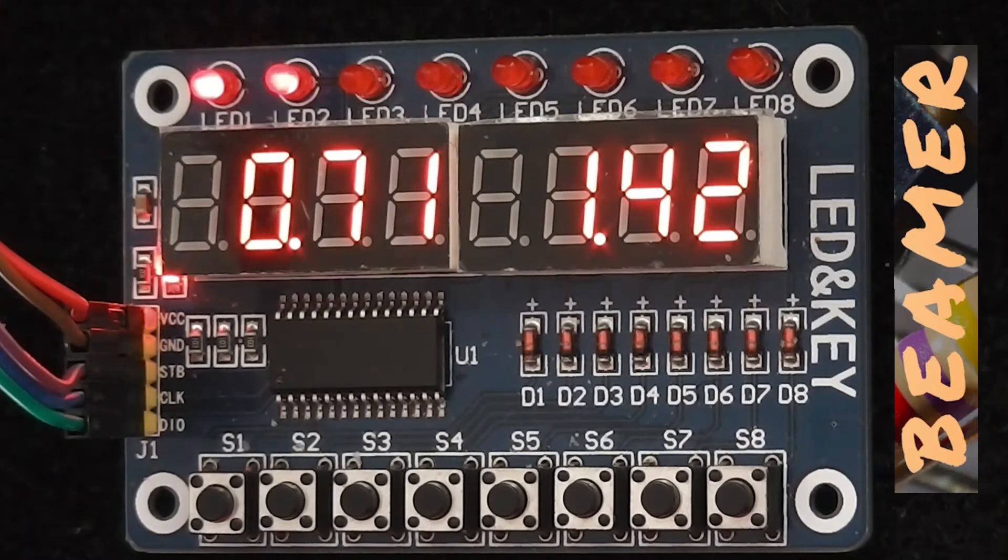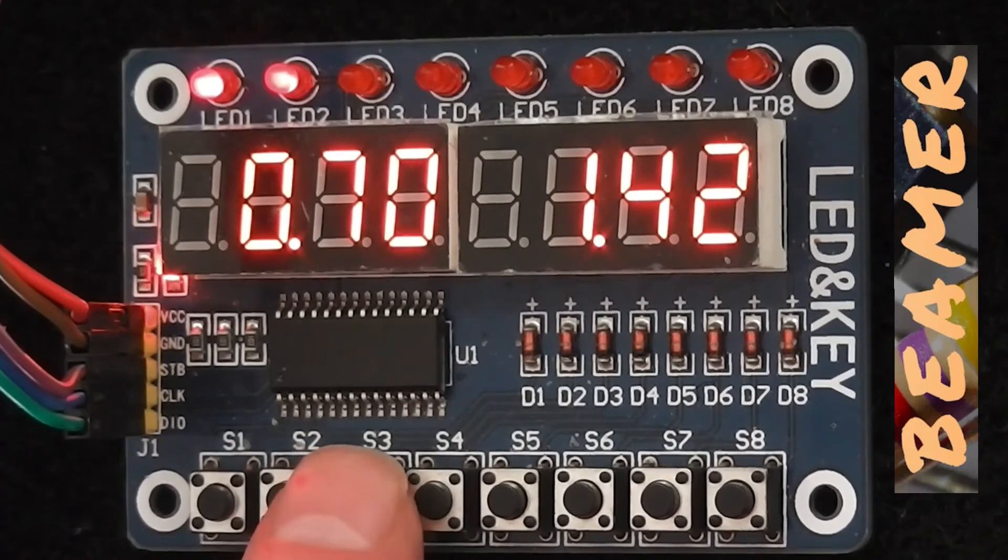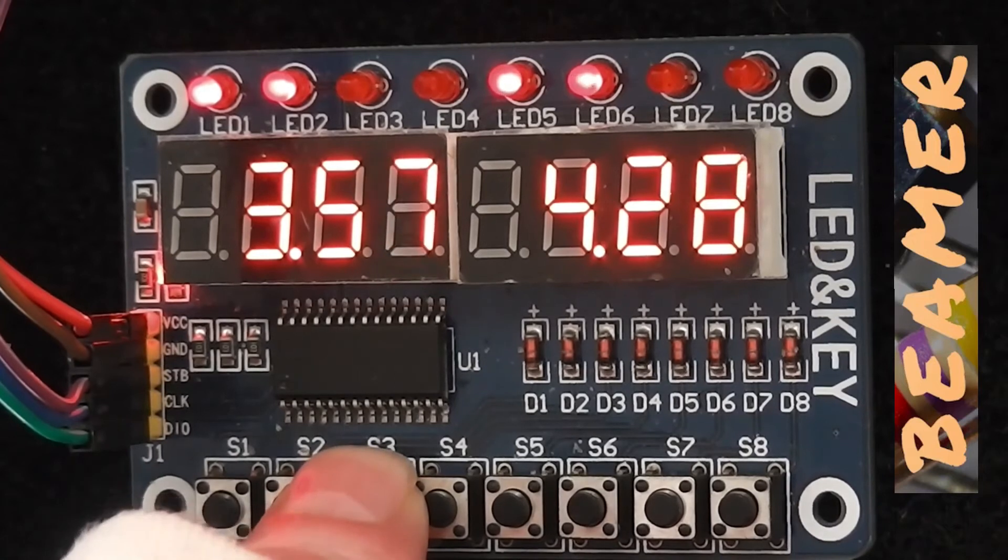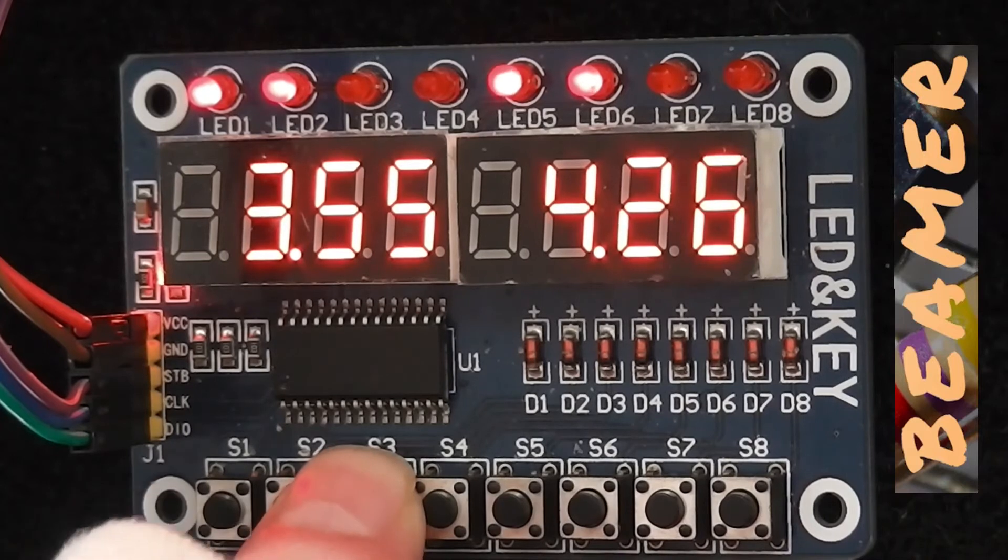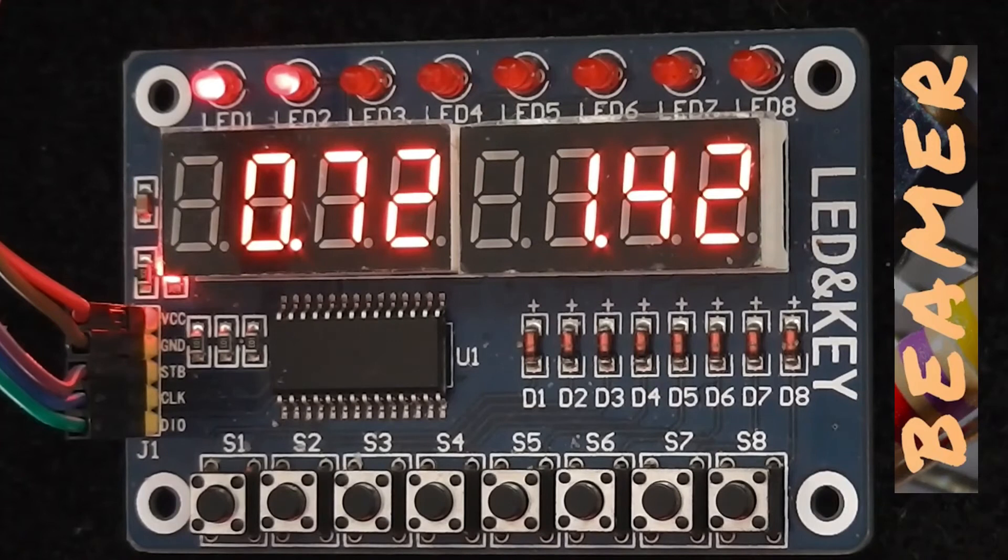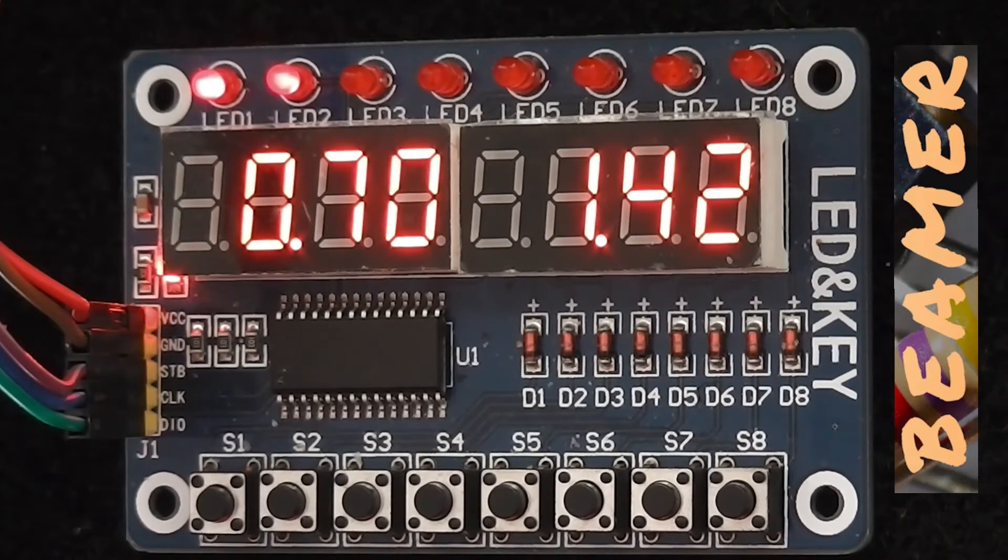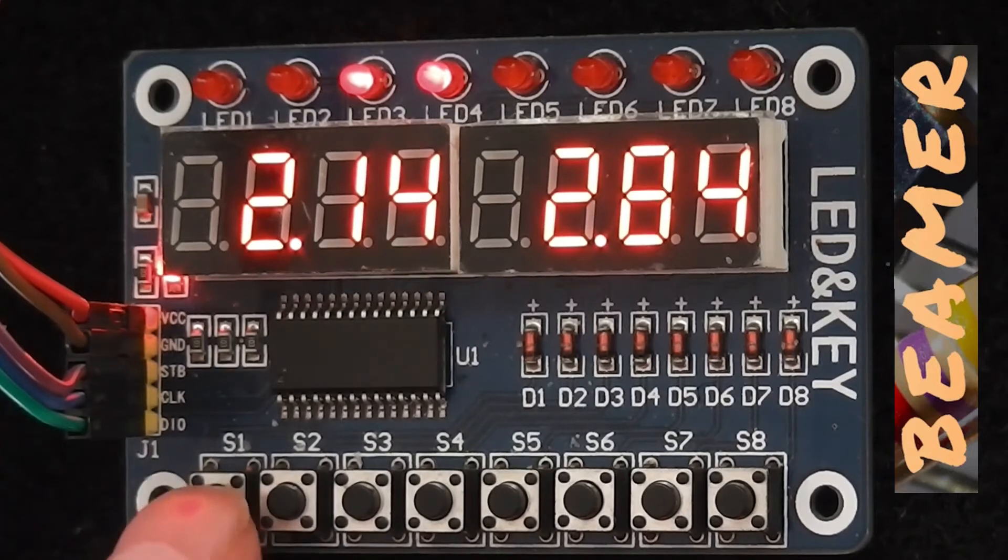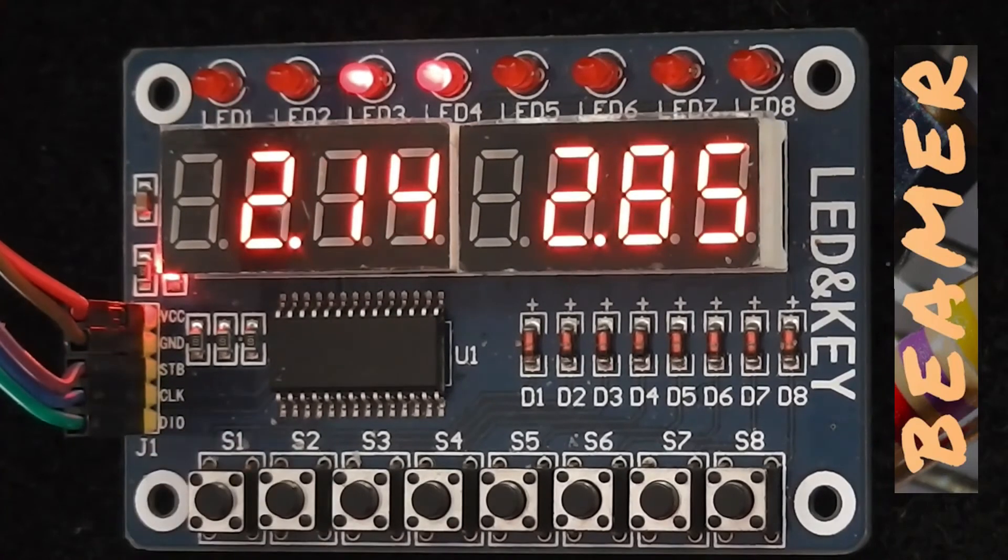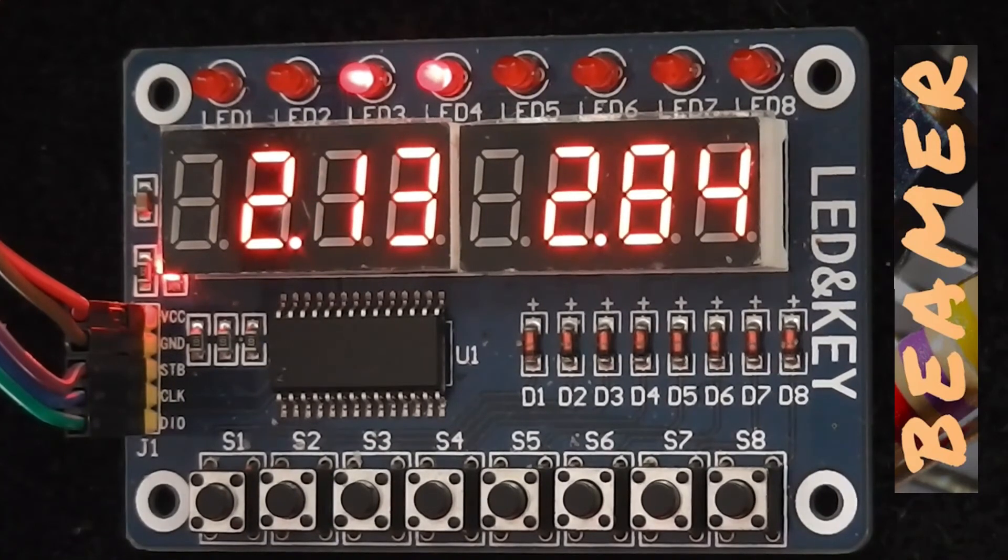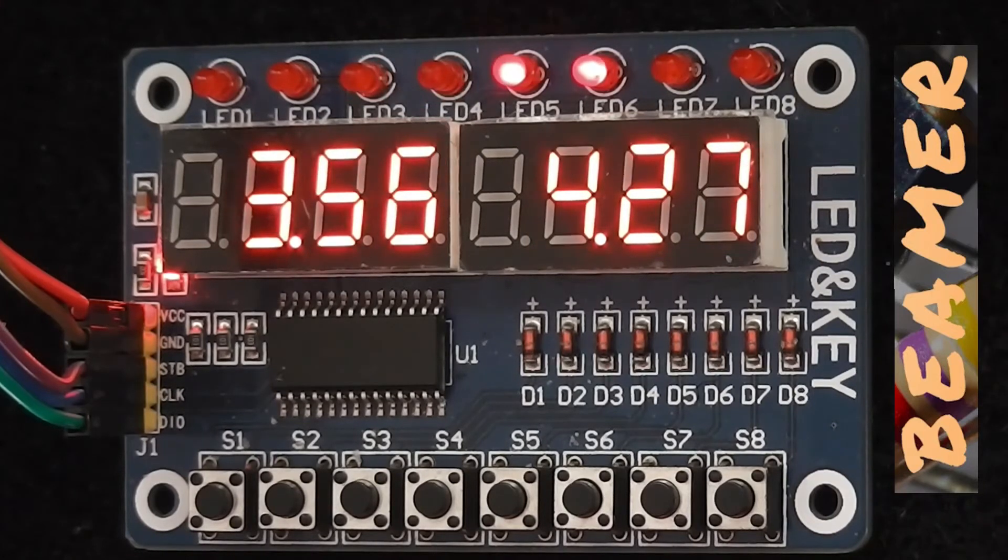If I want to look at let's say pair three I go to the third button from the left hand side there and you can see the third pair flashing and the display is displaying the voltage readings for the third pair. Release my finger and the timing circuit will then restart and go to the next scanning position which should be pair two. And there we are.